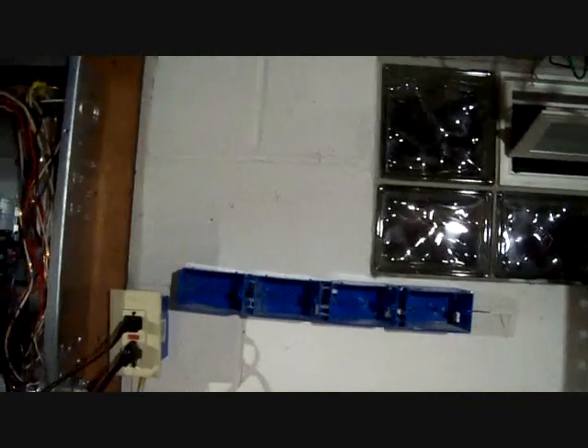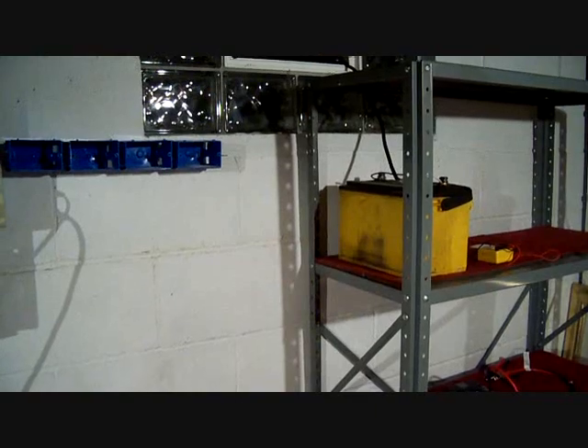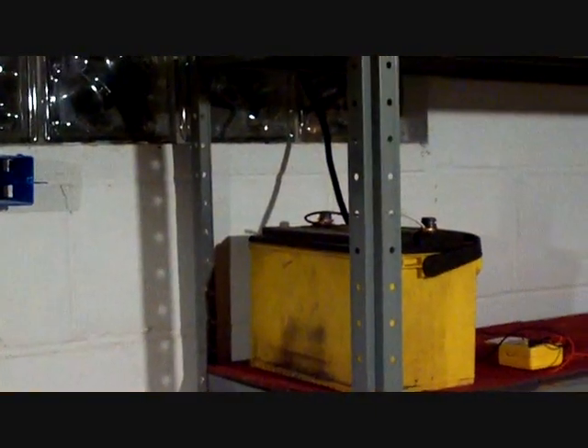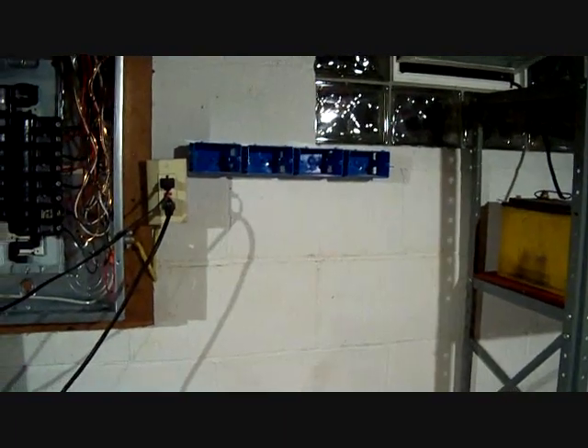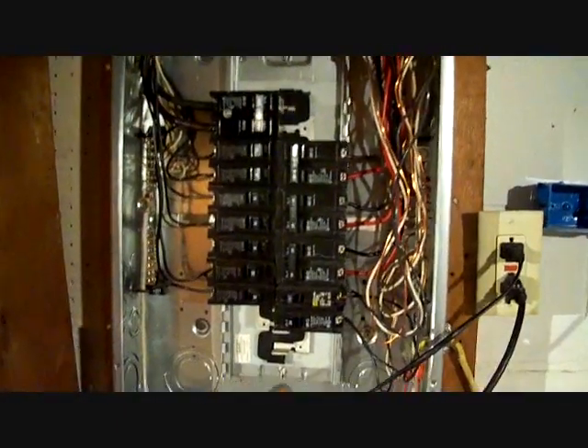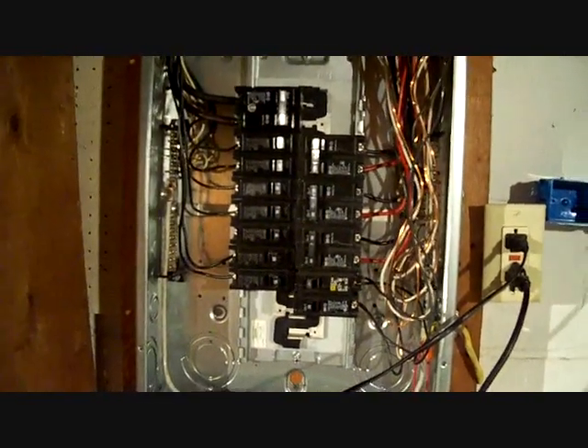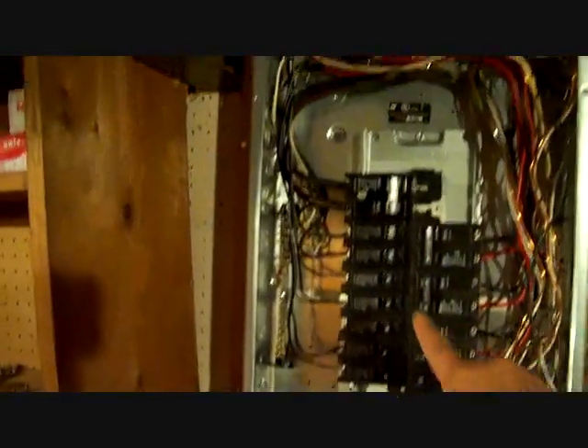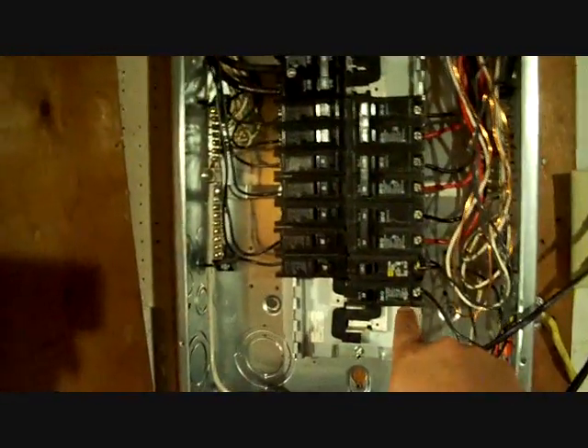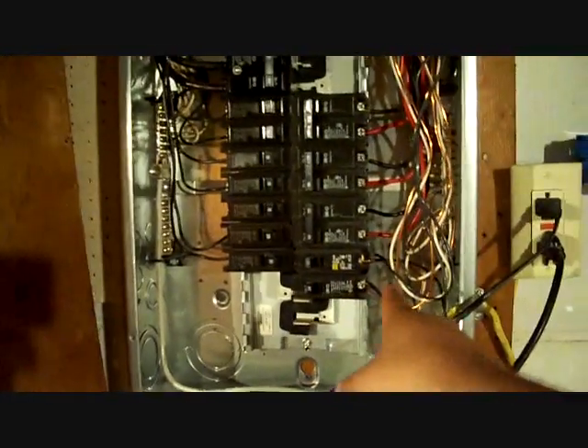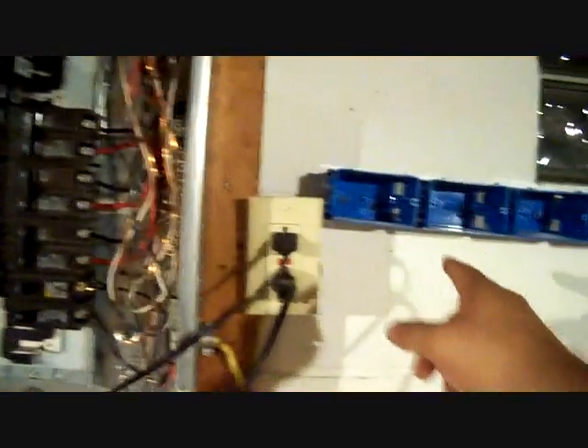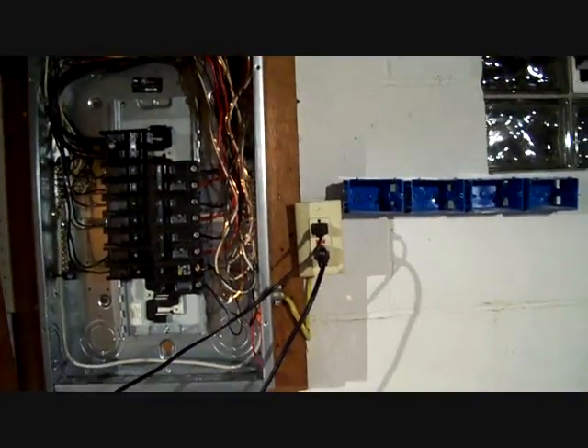And again, this is right next to where my battery bank is going to be. So that's that black wire you see right there, that's my main coming in as you've seen in the other video. I just got to get some more batteries obviously. But that's how it's going to be. They're going to be switched here and they're going to turn these breakers on and off, supplying them power other than the main power coming in. So we turn this off and have this hooked up where this black wire is. Of course, make sure that switch is off while this one's on. Vice versa, turn this one off first, then turn that one on, and you'll be using the power out of your battery bank. I'm going to show you how to do the rest of that in just a second.